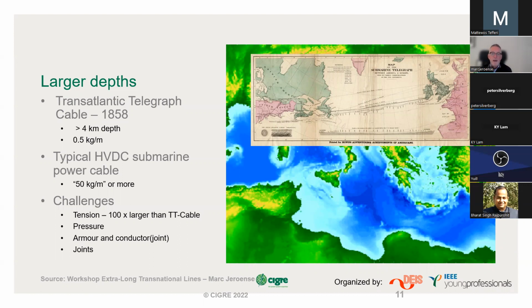And the key thing about installation of cables is mechanical tension. If the cable is being laid from the installation vessel to the bottom of the sea, the catenary, the length of the cable hanging from the vessel, becomes, of course, longer when the depth increases, and then the tension becomes also linearly larger. And if the cable already weighs more per meter, then the cable must carry its own weight. And now we are talking about many tons of cable that has to be carried by the cable itself and by the vessel. So that is one of the bigger challenges of laying a cable at large depths.